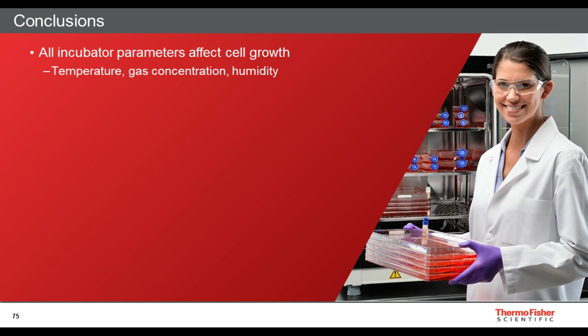So let's talk about some conclusions. Just as a review, the points I want you to remember from my talk today: all incubator parameters affect cell growth. It's not just about temperature, it's not just about pH or CO2, but also humidity plays a big role in how your cells grow. And so, as I hope I've shown you, the design and quality that goes into the incubator affect the function. The location of the sensors affects how they perform, such that in-chamber sensors will experience the same conditions as your cells. A bypass sensor, which is outside the incubator chamber, simply experiences different conditions than your cells experience, and different designs can provide different results in your process or your cell growth.